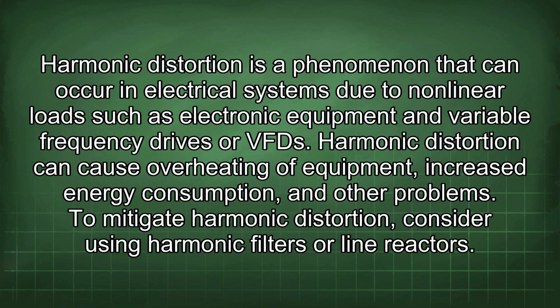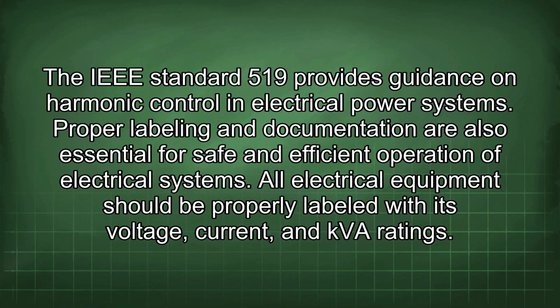Harmonic distortion is a phenomenon that can occur in electrical systems due to nonlinear loads such as electronic equipment and variable frequency drives, or VFD. Harmonic distortion can cause overheating of equipment, increased energy consumption, and other problems. To mitigate harmonic distortion, consider using harmonic filters or line reactors. The IEEE Standard 519 provides guidance on harmonic control in electrical power systems.